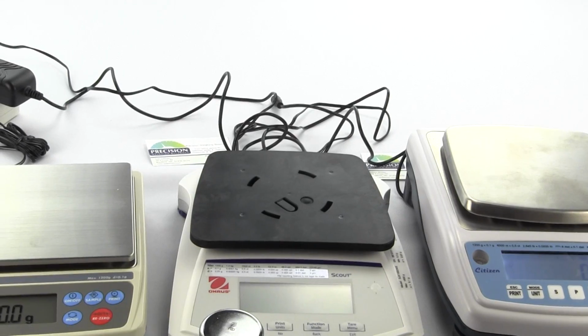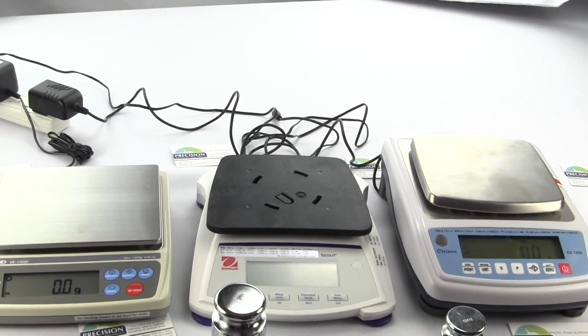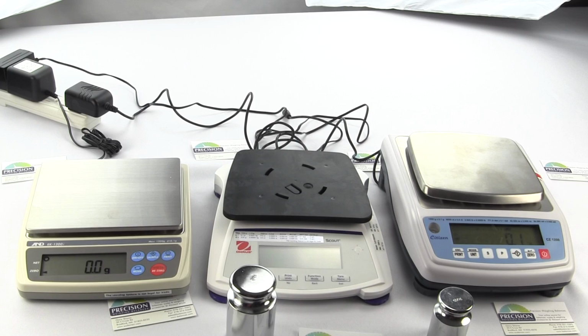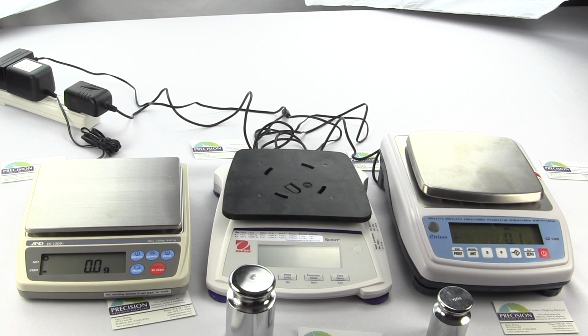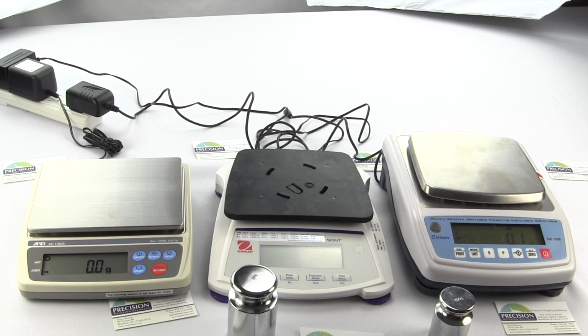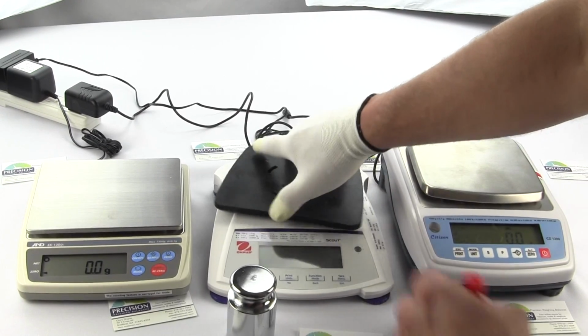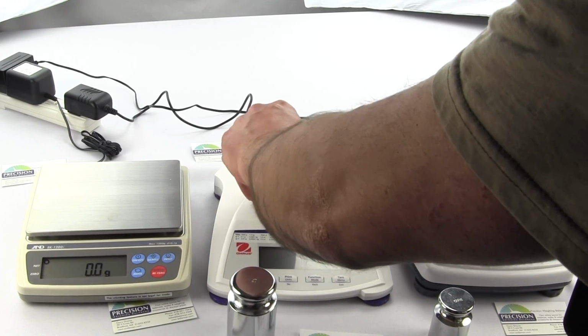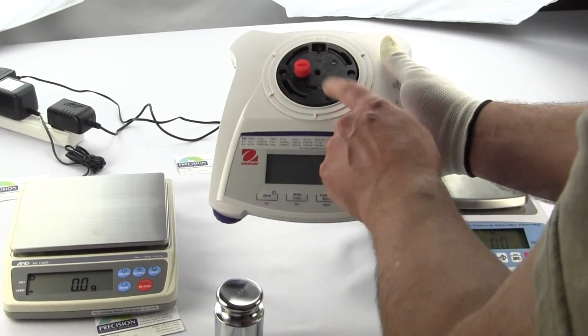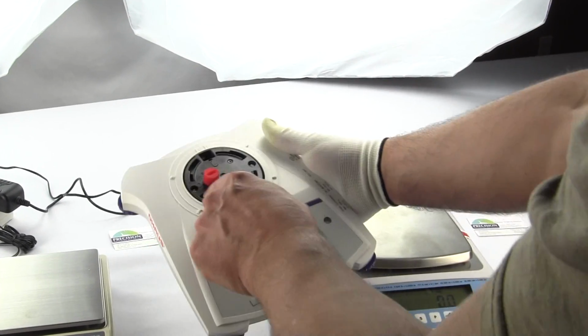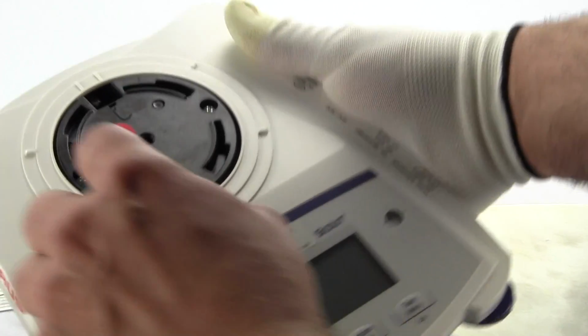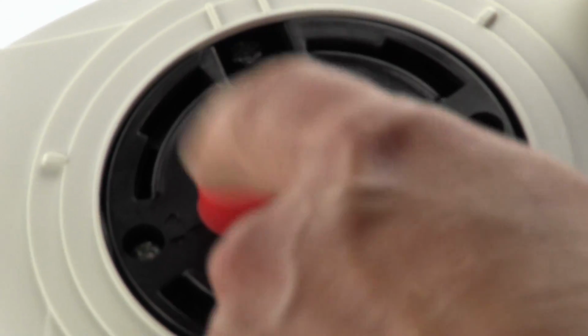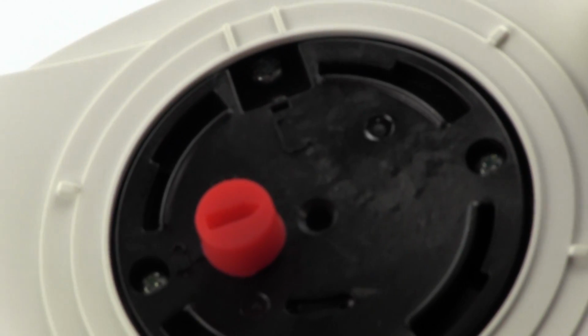There is a safety lock altogether. They call it a transportation lock. So when the scale is delivered on this Ohaus, there's this transportation lock to prevent the load cell from being damaged. So you'll see here, it's going to be delivered to you like this in the locked position. This states unlocked, but you actually have to remove this. So you have to turn it 180 degrees this way, and then it pulls out.